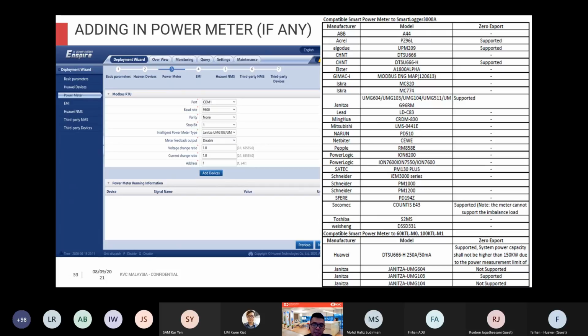Next, we look at the power meter. Due to the depletion of NEM Nova, a lot of installers and EPCs now look into self-consumption. For self-consumption to happen, you need a digital power meter. This power meter basically controls the export, doing export limitation to the grid. So in order for that to happen, you need to add the power meter into the smart logger.